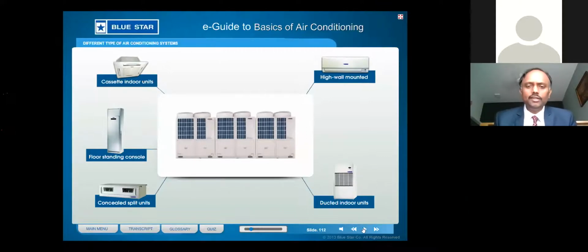The biggest beauty of a VRF system is that any type of indoor units can be connected to one common outdoor unit. So in a mall, for example, a small shop can be air conditioned with wall mount indoor units, a boutique with cassette units, a showroom with floor standing consoles, a small restaurant with concealed splits, and a theater with floor mounted package machines. All this can be combined with one common outdoor unit, the VRF outdoor unit.